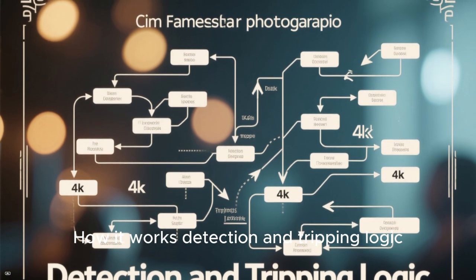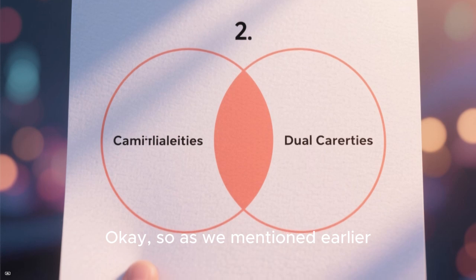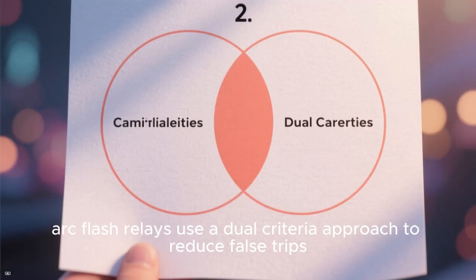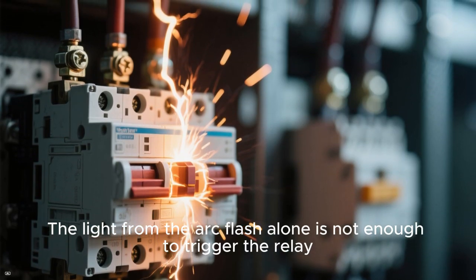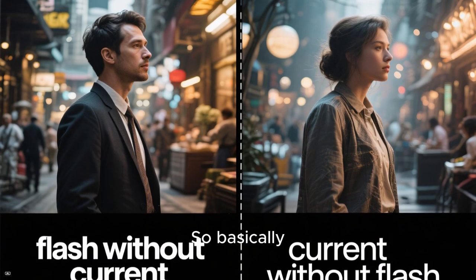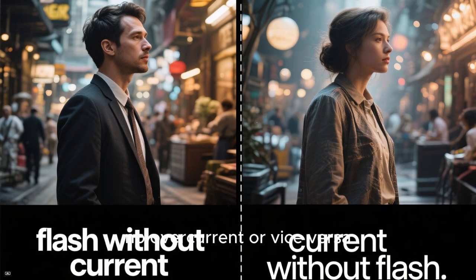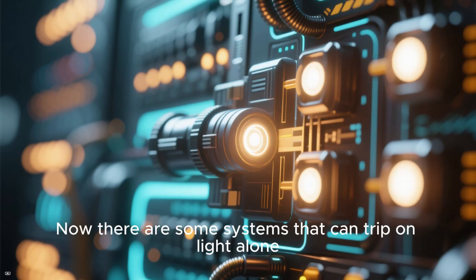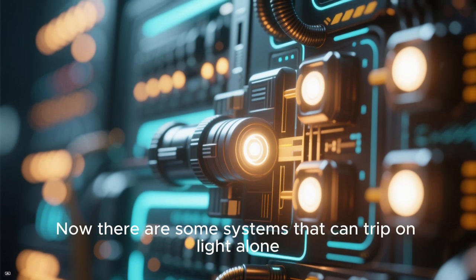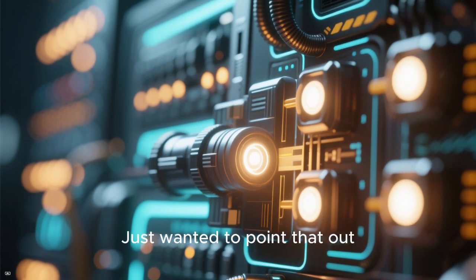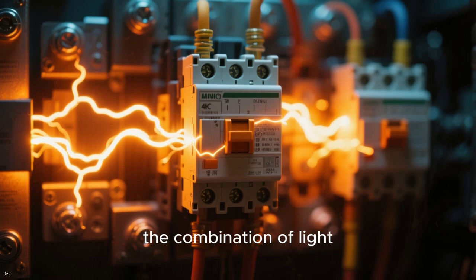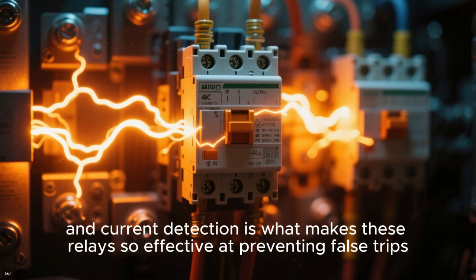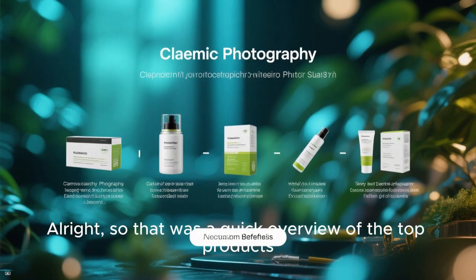Number 4, how it works. Detection and tripping logic. As we mentioned earlier, arc flash relays use a dual criteria approach to reduce false trips. The light from the arc flash alone is not enough to trigger the relay. It has to be accompanied by overcurrent. So basically, if there's an arc flash but no overcurrent or vice versa, the relay won't trip. Now, there are some systems that can trip on light alone. That's configurable. Just wanted to point that out. But generally speaking, the combination of light and current detection is what makes these relays so effective at preventing false trips. Alright, so that was a quick overview of the top products.